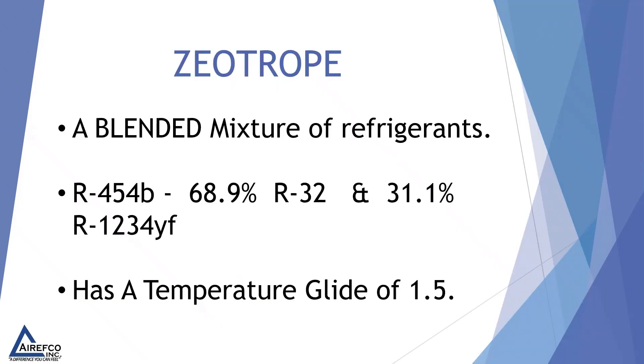The reason you have double columns for some refrigerants on your PT chart is because some refrigerants are classified as a zeotrope mixture, meaning they are a blended mixture of two or more refrigerants. The R454B refrigerant coming to market soon is a mixture of R32 at 68.9% and R1234YF at 31.1%, and it has a temperature glide of 1.5 degrees, so it is a mixture.